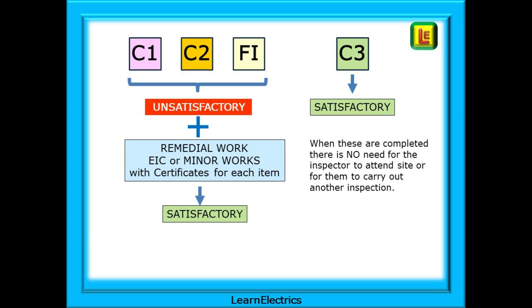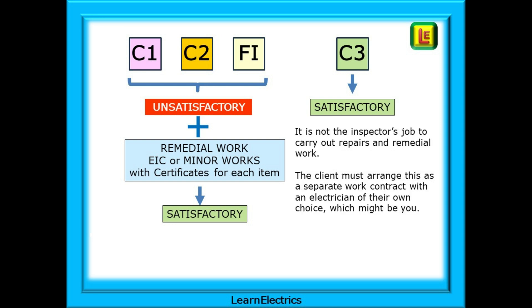Any C1, C2, or FI will automatically make the EICR unsatisfactory — a fail, if you like. Given the conditions that you observed, the installation is not in a satisfactory condition for continued use. This does not mean that the installation cannot be used by the client. It means that the client must take steps to rectify the issues noted within a reasonably short time. If it's a business, the client will usually be expected by the insurance company to put a plan in place to bring the installation up to the required standard. This is achieved by remedial work being carried out and each item being recorded as completed and satisfactory on either an EIC or minor works certificates. When all the work is completed and certified, the installation will automatically become satisfactory.